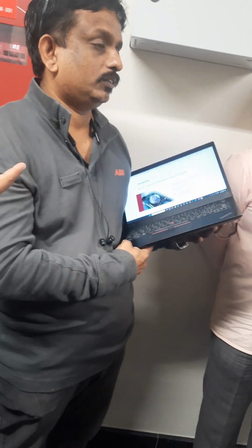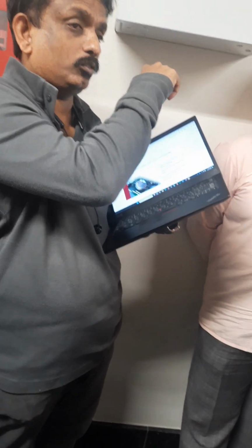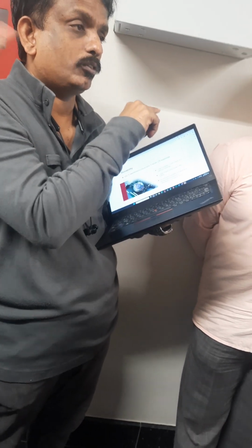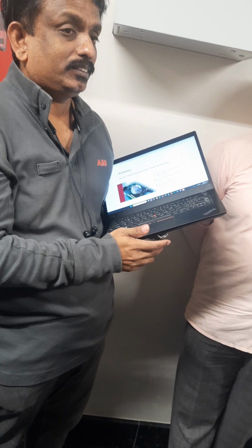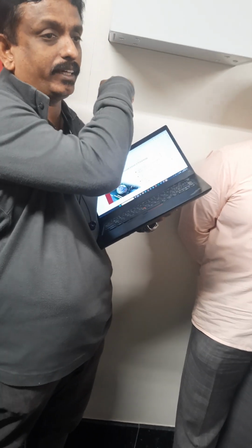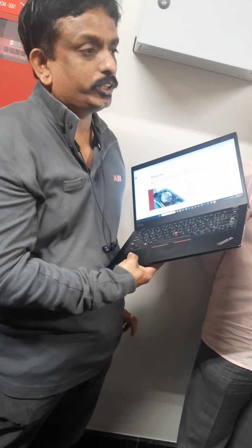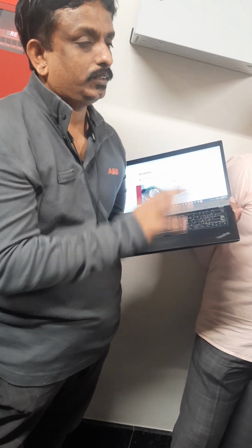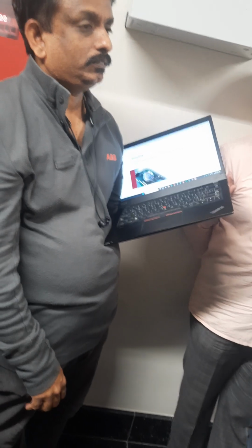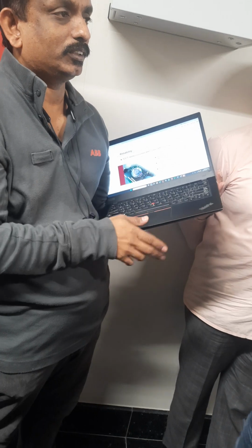Which battery do we need to monitor? The UPS supply for the HV breaker, the breaker in the MV switch gear. I am talking about the breaker; you are providing supply to the breaker. It is the battery charger, the one highlighted, the battery charger. You always need to monitor all functions of it.